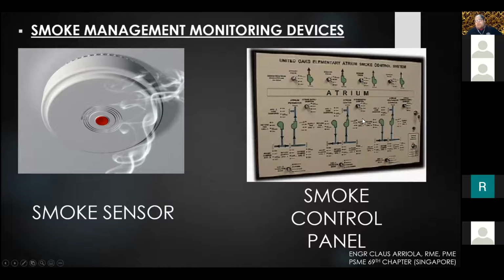And then this smoke control panel is usually located in the FCC room or fire command center. It should be independent of your fire alarm panel. Okay, it should be independent of your fire alarm panel. This one indicates which zone. If you can see, this indicates the zone, because if this fan is activated by a certain smoke sensor, then this one will run. Then you already know which zone has a fire scenario.